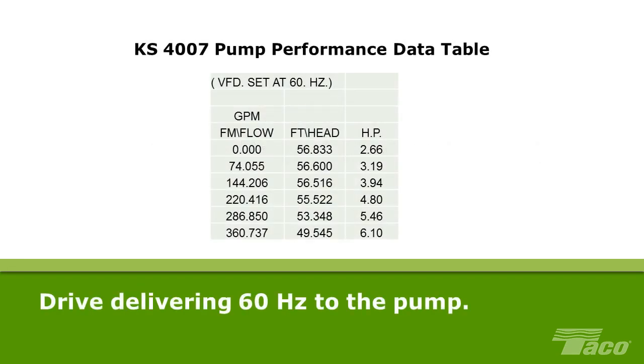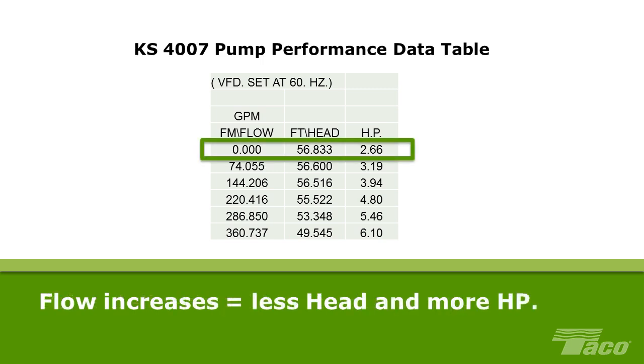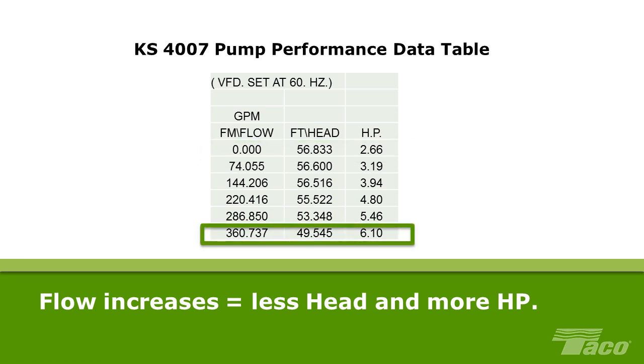Here's a pump performance data table for the Taco 4007 self-sensing pump with a VFD delivering 60 Hz to the motor. At zero flow, the pump creates just under 57 feet of head and a little over 2 horsepower. As the flow increases, so does the horsepower, while the head decreases. At a flow of a little more than 360 GPM, the pump generates 49.5 feet of head and 6 horsepower.